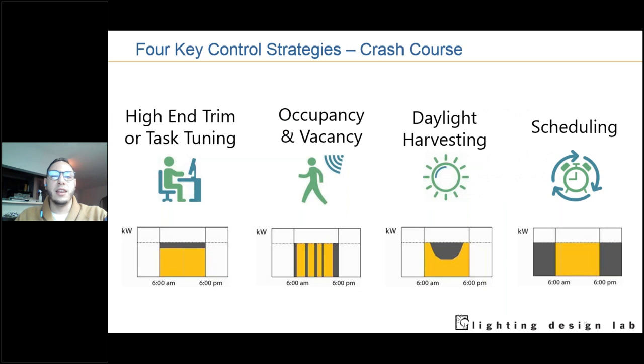I want to review four key network lighting control strategies, starting with high-end trim or task tuning. That's the ability to cap a ceiling on the maximum brightness of a luminaire's output—that's why you see the gray over the yellow here under task tuning. It's a ceiling on the maximum output that cannot be updated or changed without a commissioning tool, be it a remote, a phone, or a computer. This is done because fixture lumen packages are specified conservatively and with good reason—fixtures are usually made brighter than needed for the space they're meant for.